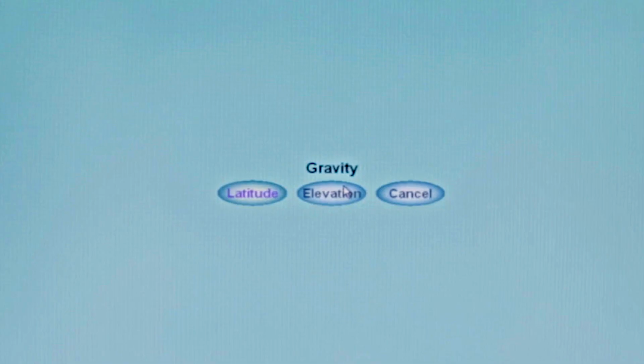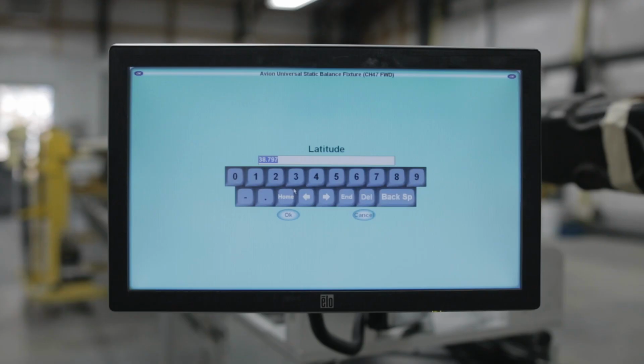Gravity. These settings are required for your fixture to function at your current location. Under Gravity, we have 2 submenus. Latitude. You can take this machine to different locations around the world. Latitude is required because electronic scales measure gravity differently depending on your location. Centrifugal force at the equator is pushing you out because of the rotation of the Earth, so your weight is less there than at the poles where there is no centrifugal force and you have true weight. You can get this data for your location off of instrument approach charts from a pilot or off the internet.